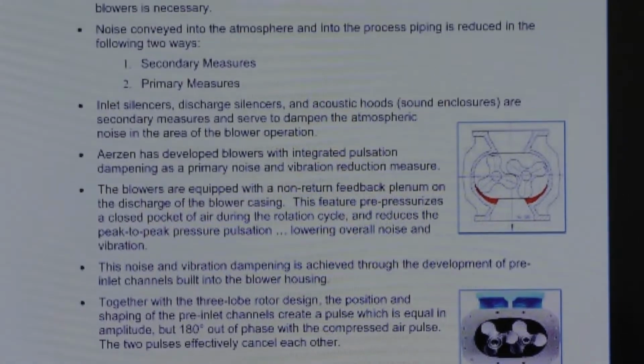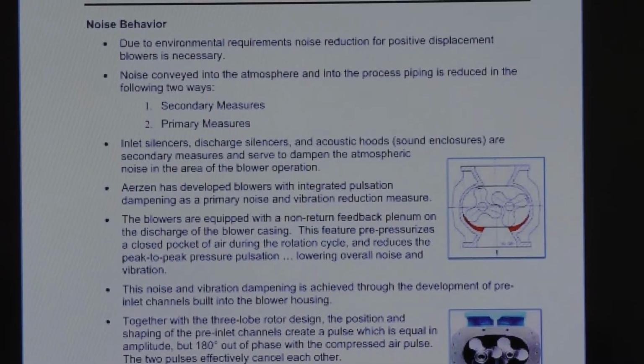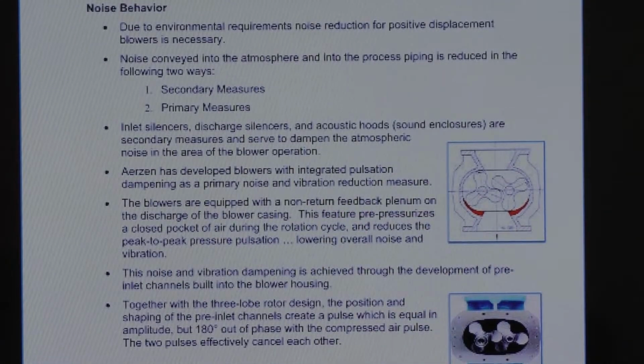All right, as you're looking at the stage, this is what the inside of the tri-lobe blower looks like. It pulls the air in, your rotors rotate to the outer direction, pull the air down and push it out. Now, there is some noise from that process of the rotors coming together and compressing the air slightly as it moves it through.